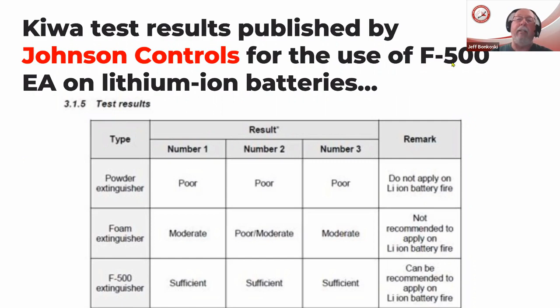We start looking at the published report by Johnson Controls after the testing was done. In the series of tests they conducted, the powders were poor, not recommended, do not apply. The foams were moderate to poor, also not recommended to apply on lithium-ion battery fires. The F500 was sufficient all the way across the board. If you do a Google search for Johnson Controls and lithium-ion battery fire protection or fire extinguishers, you'll see that over in Europe they are actually selling fire extinguishers with F500 in it.